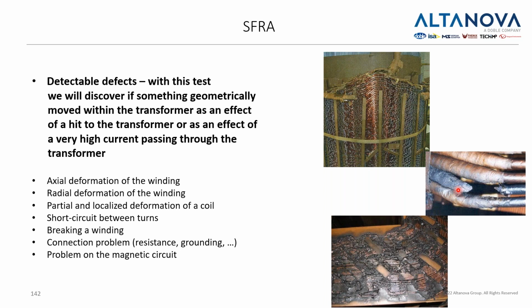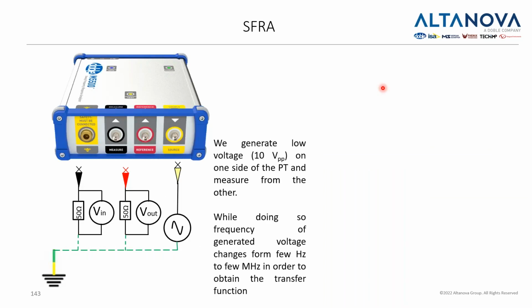So you can see axial deformation, radial deformation, partial and localized deformation of a coil, short circuit between turns, breaking of the winding, connection problems, and problems with the magnetic circuit. And you can see all these pictures here. Here we have, let's say, breaking of a winding. Here we have deformation of the winding, and a small device is needed to do this. In this case, the M5500 will generate low voltages.